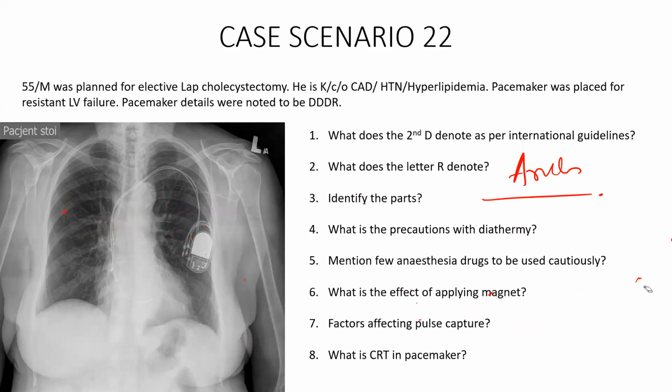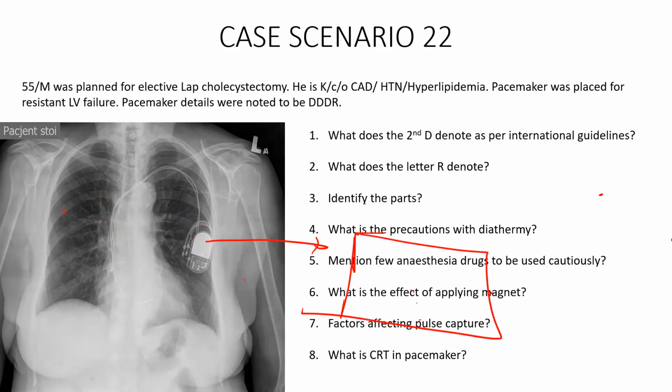Sir, how to reprogram it immediately? Yeah, there is a Wi-Fi link. The pacemaker physician has to be there when you're doing the surgery, and they will teach you how to get linked with the pulse generator. Once you get a Wi-Fi link with the system, there is an option of reprogramming immediately, and you can switch on the anti-tachycardia function. Okay, sir.